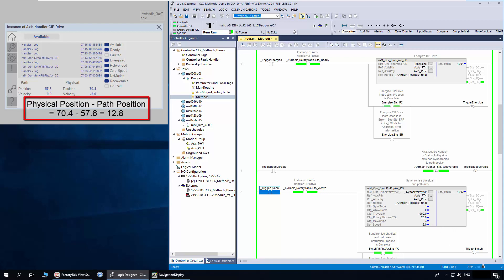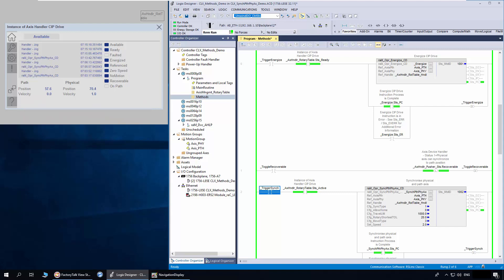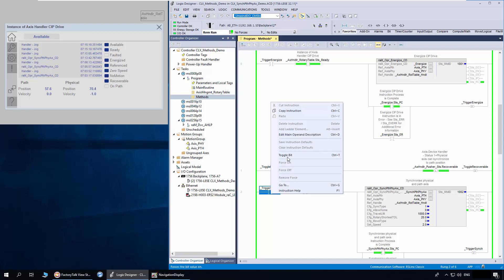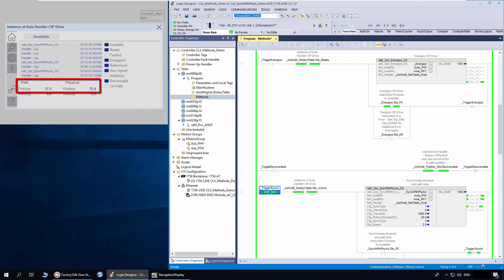In this scenario, since the recovery distance of physical axis is within the limit of 20, the physical axis will do a reverse movement instead of a long forward movement. The handler energize status is on, I will trigger the sync method. You can notice the physical axis is moving in reverse direction, and now in sync with path axis.